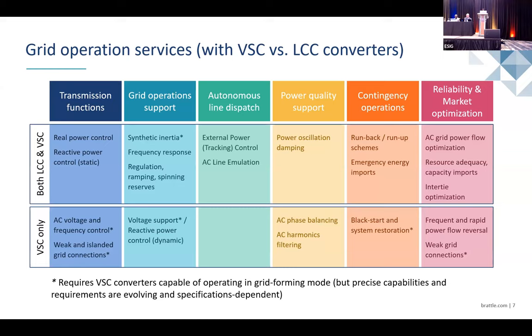And we can restore the network, basically. Similarly, with a VSC, because of the nature of the converter and how it operates, we can change the power flow any number of times. Whereas with the older technology, LCC, you can't do power reversal like that. But with VSC, you can do power reversal immediately if you want. VSC also offers one more benefit: we can connect the VSC converter to weaker grids. Whereas with legacy LCC converters, you have some problems. We can't connect an LCC converter to all types of grids, whereas with VSC, we can connect to any type of grid.